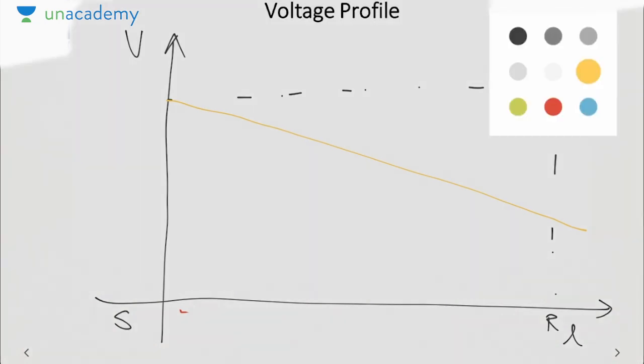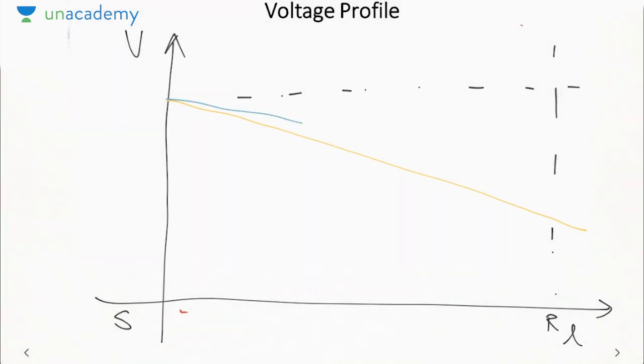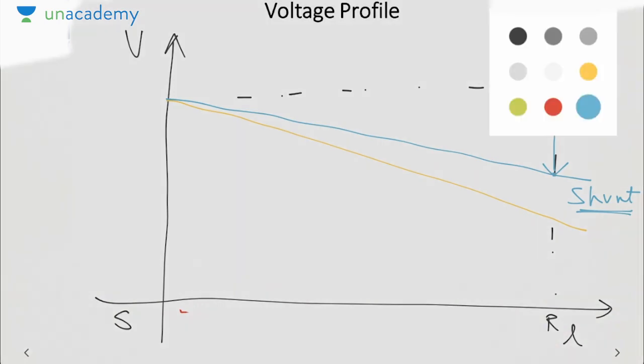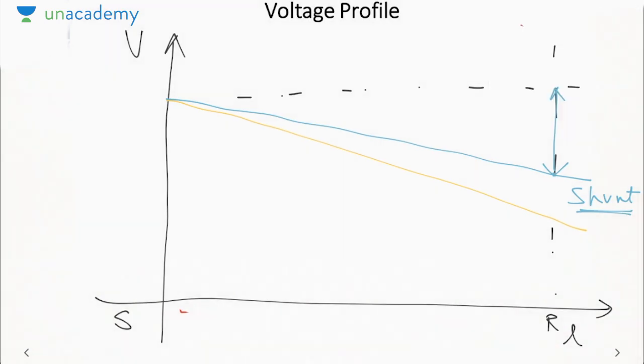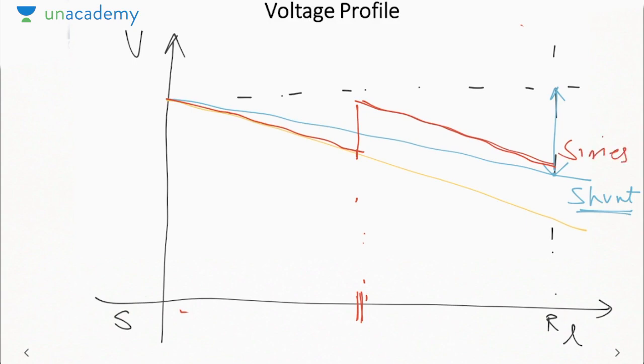Now with the shunt compensation, we will change the slope. We will reduce the slope. So this is with shunt. Okay. If you see, receiving end voltage has increased or the voltage drop has reduced. What happens with series? The slope remains same. There is just a shift. Now suppose the capacitor is connected at midpoint. Up to midpoint, the curve will remain same. But as soon as midpoint comes, there will be a shift in the characteristic. Again, it will follow the same curve. So that will be the case for series compensation.